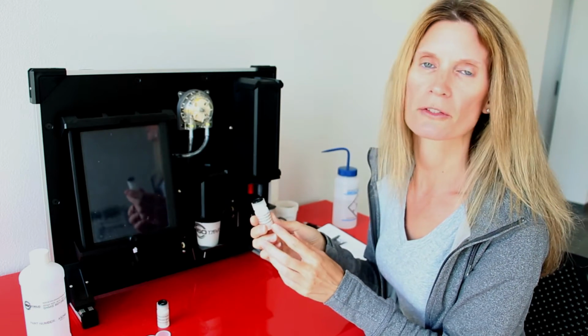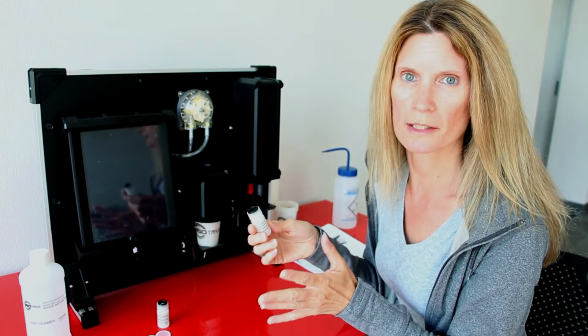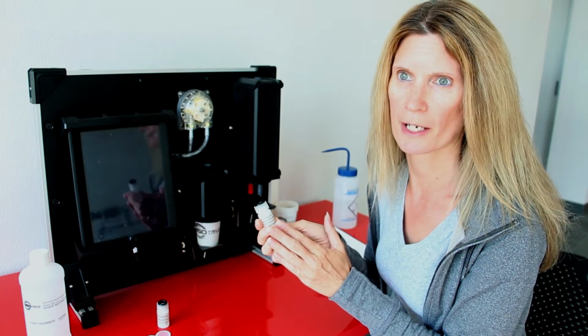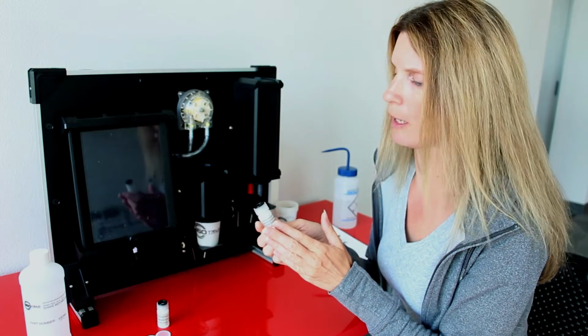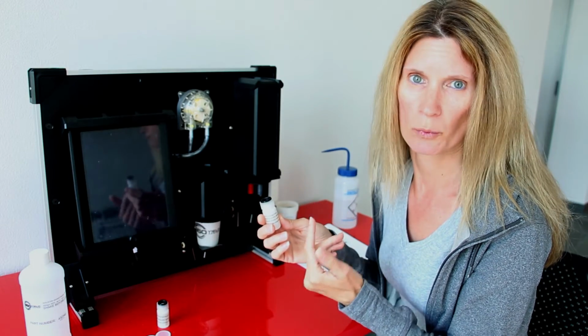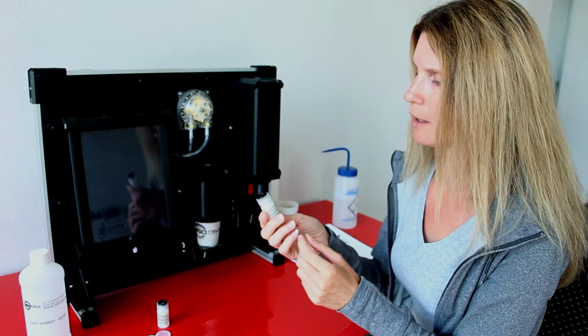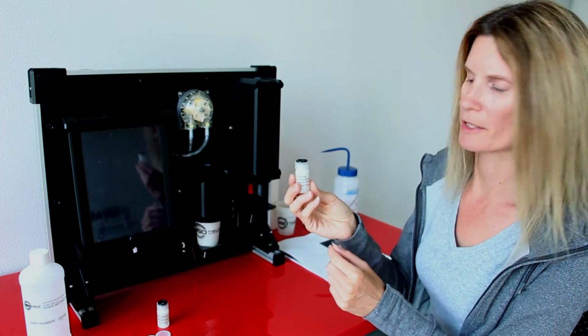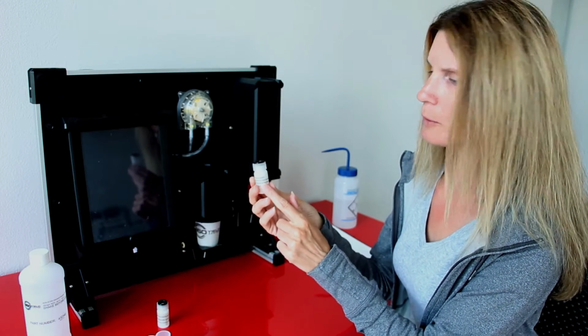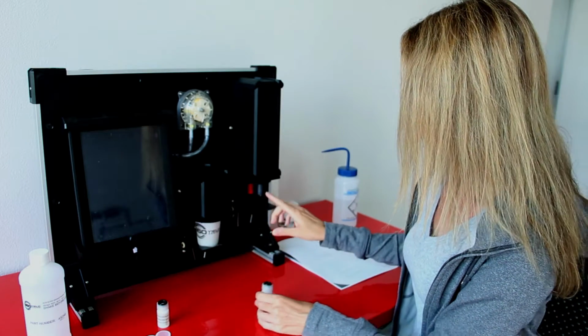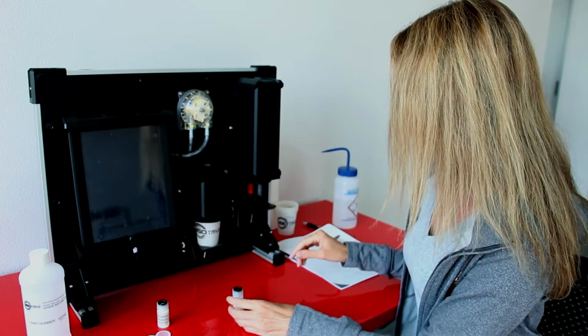Now it's very important to follow this carefully because we have one that's stored wet and one that's stored dry, so be aware which one we need to store dry and which wet. So first off, we're going to take the NO3 storage bottle. This says to always store the sensor dry. This is for your gray nitrate sensor here.